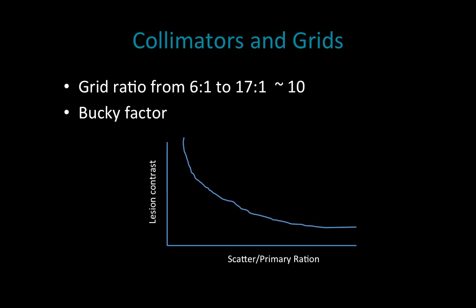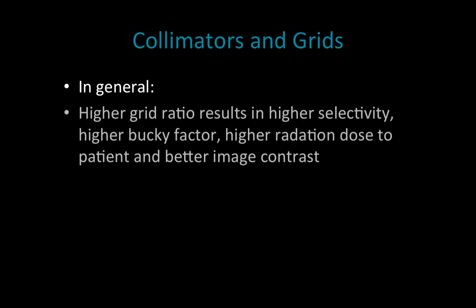For example, a structure with a thickness of about 12 centimeters will probably need a grid. Usual grid ratios range from 6:1 to 17:1, with 10:1 being typical for radiography and fluoroscopy. In summary, a higher grid ratio results in higher selectivity — fewer x-rays pass through the grid — which results in a higher bucky factor, a higher radiation dose to the patient, and the benefit of better image contrast.